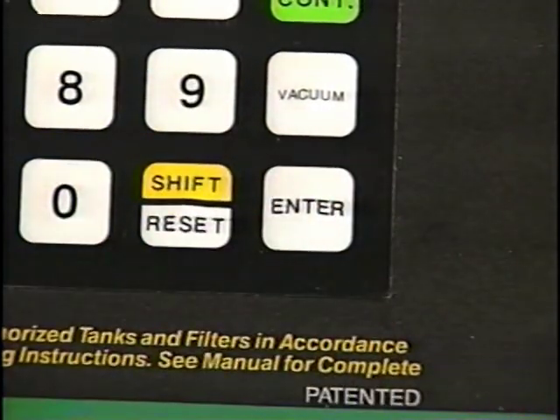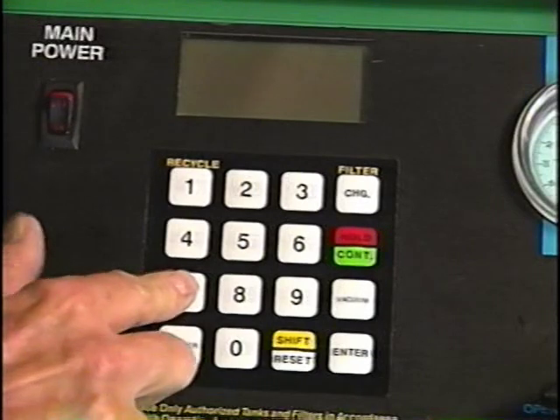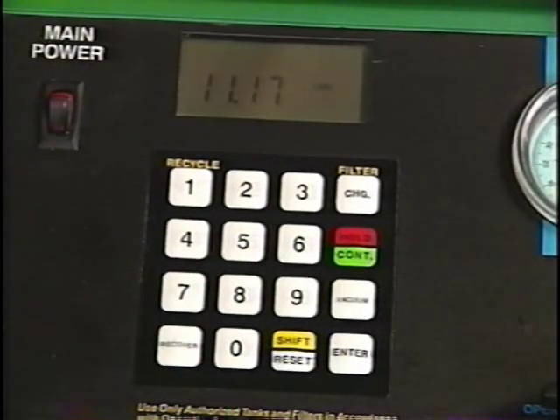Before evacuating the system, we'd like to check the ACR4 tank unit to make sure that we have the correct amount of refrigerant to recharge the system. In order to do that, we would hit the Shift-Enter keys simultaneously. The 7 key, shown on the panel display here, will give the amount of refrigerant remaining in the tank. If that tank level is below 8 pounds, we're going to have to refill that tank with the correct amount of refrigerant so that we can continue our process of recharging the system.